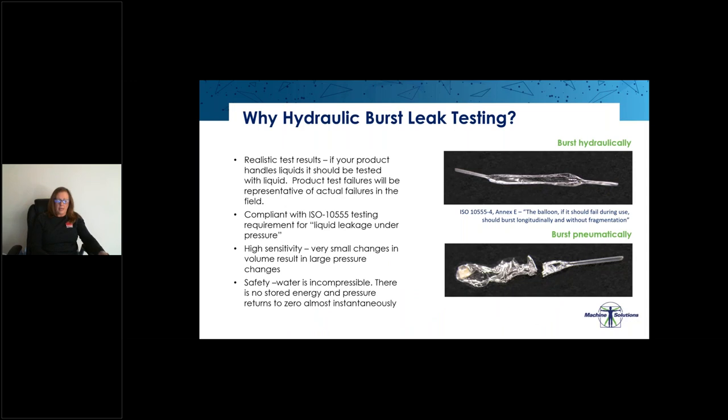People often ask me why hydraulic pressure testing. The biggest benefit or reason for testing hydraulically is that balloons and catheters are pressurized hydraulically in the field. And if our product handles liquid, it should be tested using liquid.